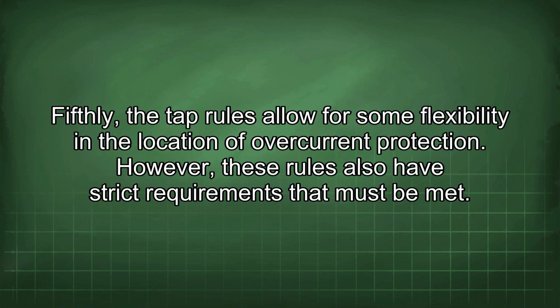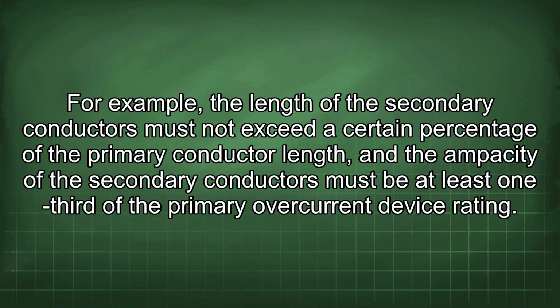Fifthly, the tap rules allow for some flexibility in the location of overcurrent protection. However, these rules also have strict requirements that must be met. For example, the length of the secondary conductors must not exceed a certain percentage of the primary conductor length, and the ampacity of the secondary conductors must be at least 1/3 of the primary overcurrent device rating.